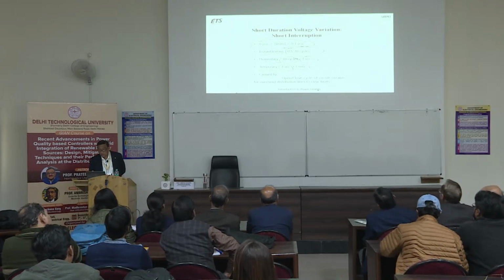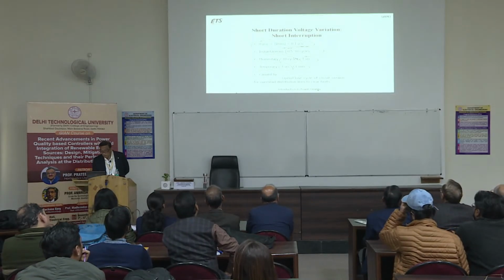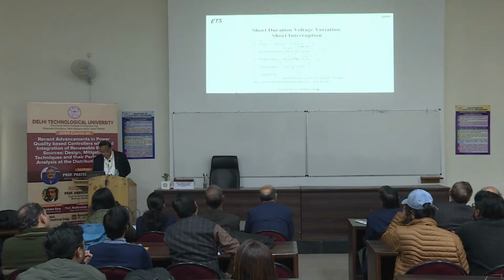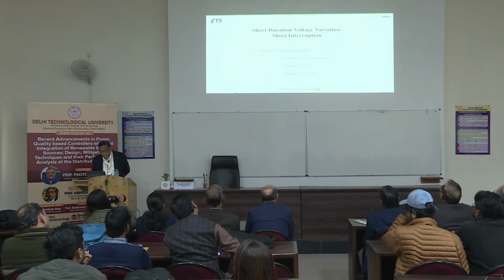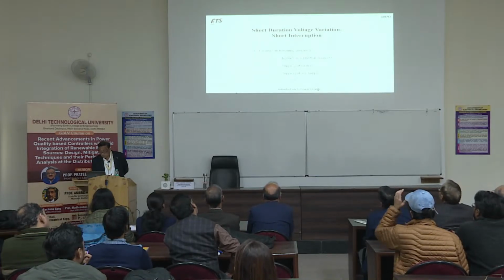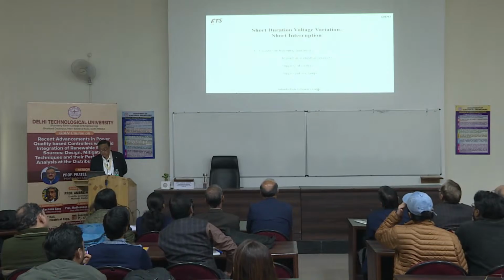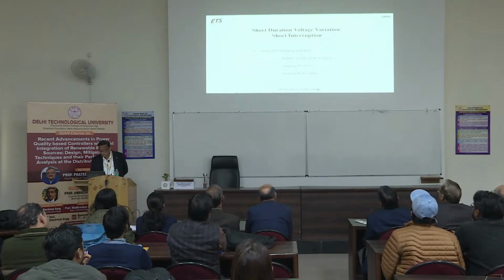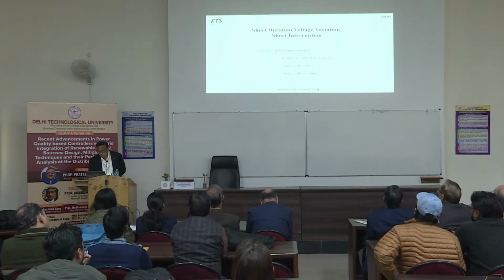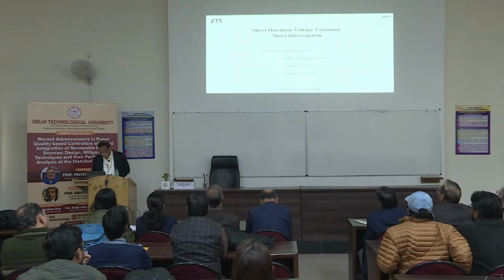So these are short interruptions caused by open close cycle of circuit breaker of overhead transmission distribution line. It may cause the following problems: impact on industrial product, as we were discussing, tripping of motors, tripping of arc lamps.